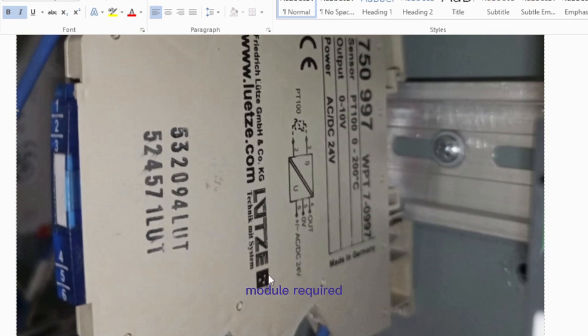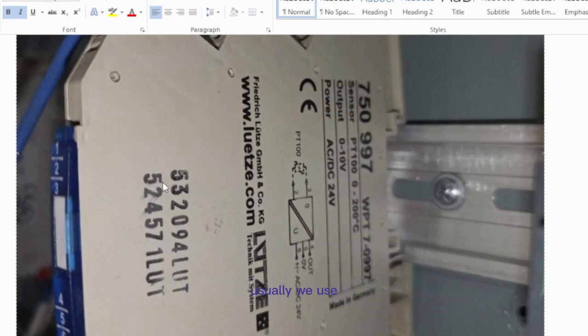The module requires 24 volt DC or AC. Usually we use a DC power supply for this kind of module, otherwise we have to use a 24 volt step down transformer. The cost for the transformer is expensive, so we use a 24 volt power supply, as we are already using 24 volt control in our panels.